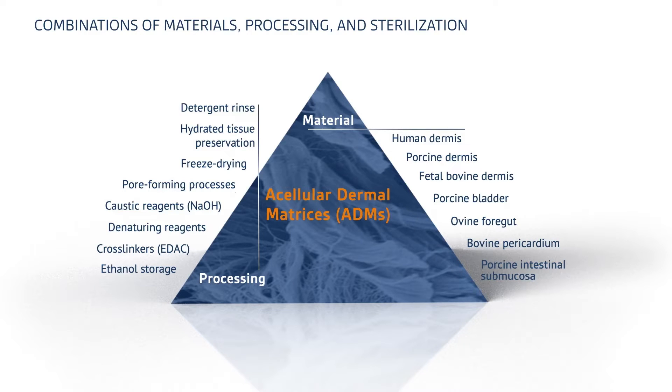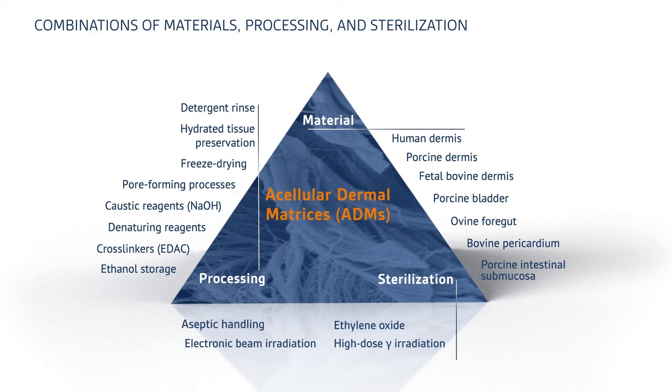The final factor that can affect the properties of an ADM is the sterilization method. This too can vary greatly, from aseptic handling to high-dose gamma irradiation. The key takeaway here is that, with so many different types of surgical scaffolds available, it's important to understand that all the various combinations of materials, processes, and sterilization methods will yield ADMs with different structural and functional properties — and this can lead to different results when implanted in the body.